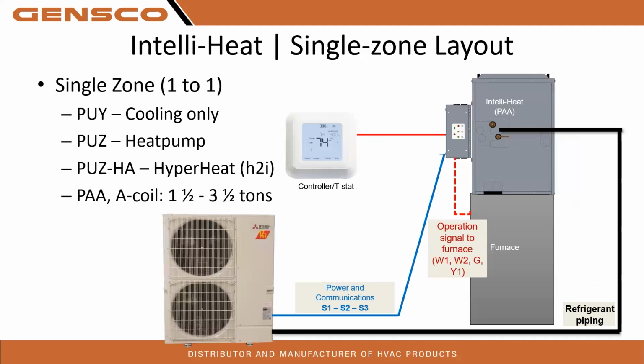Right here, this is a good example of what the Intelli-Heat is. This is an example of a one-to-one system. As you can see, we got our one-to-one PUY or PUZ heat pump with our Intelli-Heat coil sitting on top of our gas furnace. On a one-to-one system, it can be used as a cooling only on a PUY. It can be hooked up to a PUZ heat pump, a hyperheat, anywhere from 1.5 to 3.5 tons.